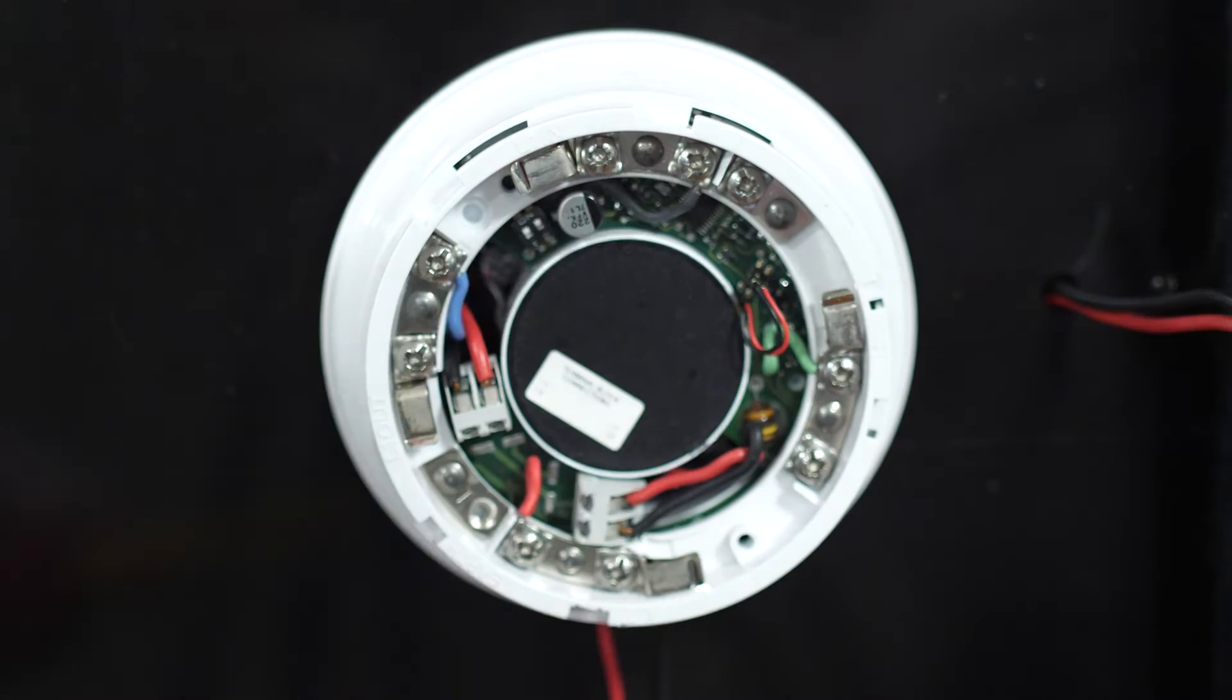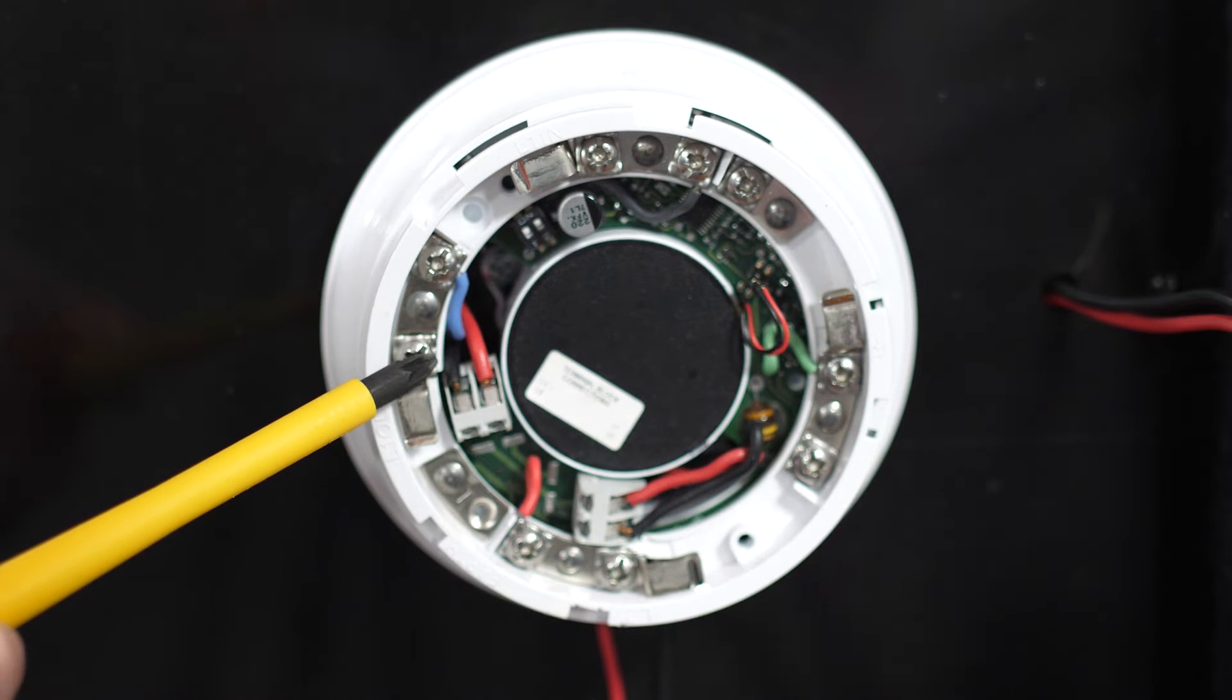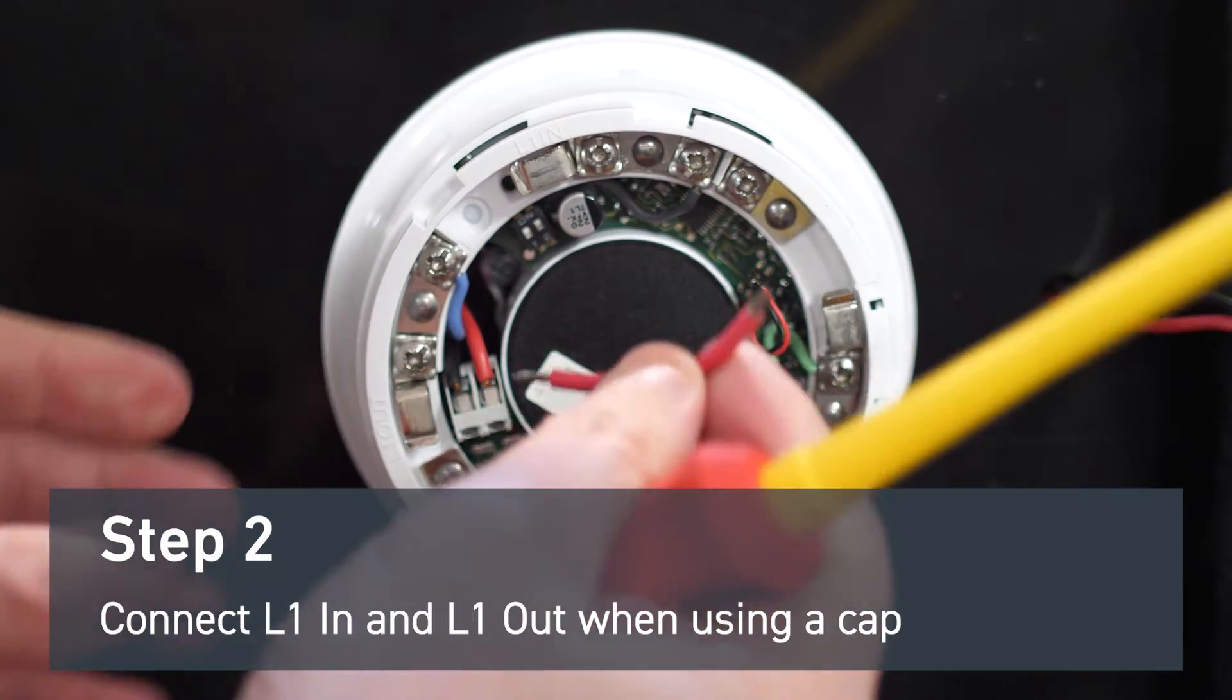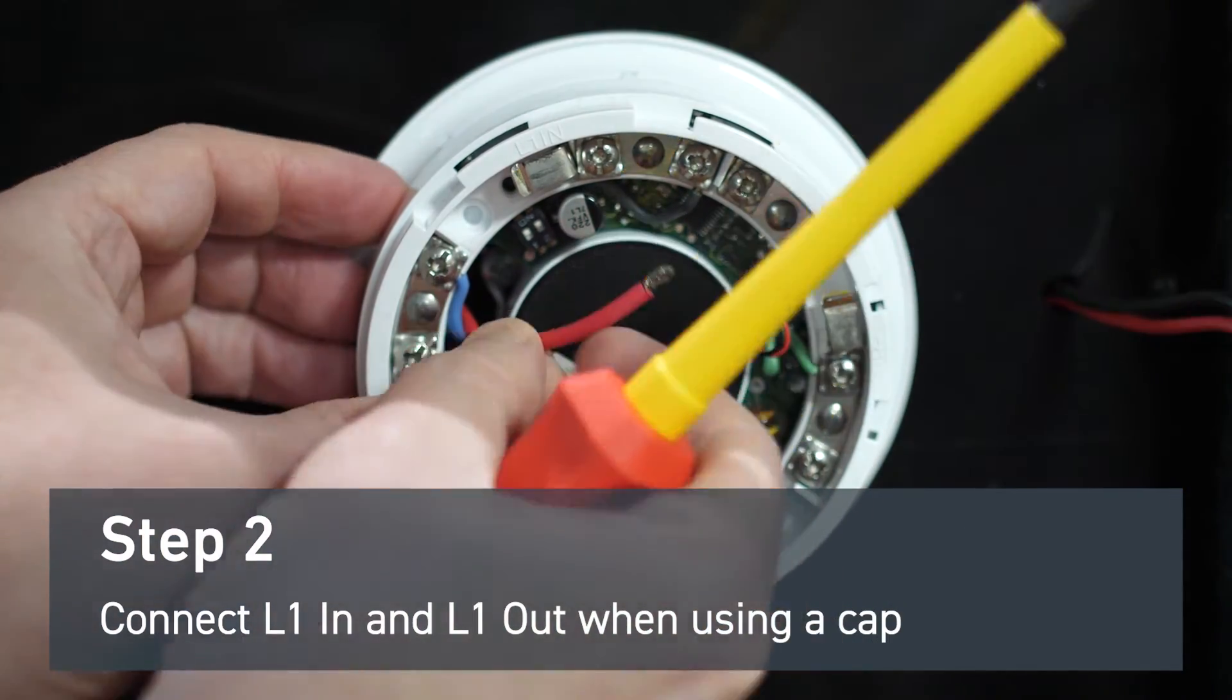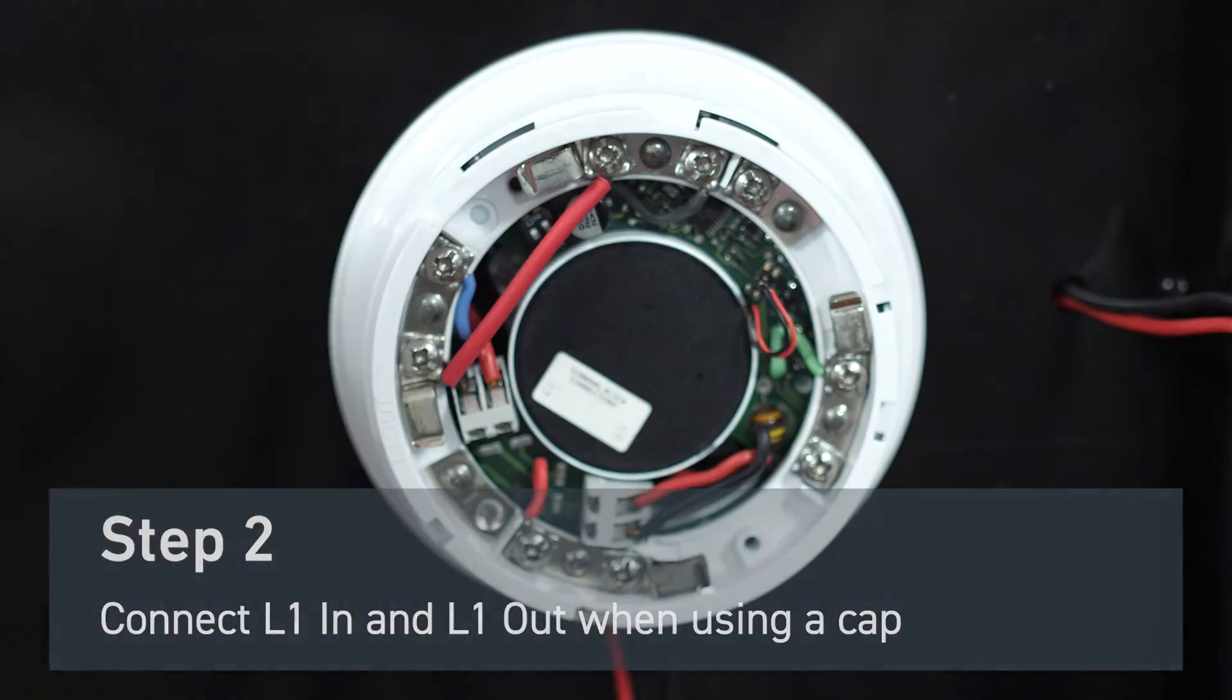If you're not fitting an alarm sense detector but instead fitting a cap, then you will require a wire link between the outer ring terminals L1 in and L1 out. If you don't fit the link, then you will get a head removal fault at the fire alarm panel.